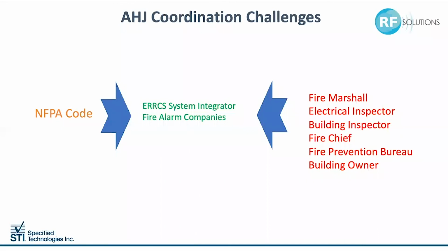The IFC and NFPA typically update codes on a 3-year cycle. The frequency of change for local codes can vary. Processes and procedures can lag behind these changes in national codes. State and local jurisdictions adopt national codes through ordinances and set the rules and regulations for public safety in-building radio enhancement systems. These codes, in turn, reference standards that must be adhered to. For instance, IFC 510 makes many references to standards in the NFPA code.